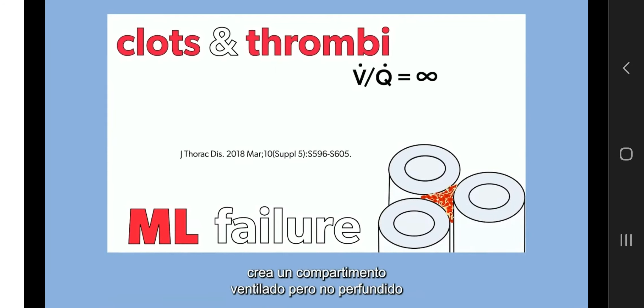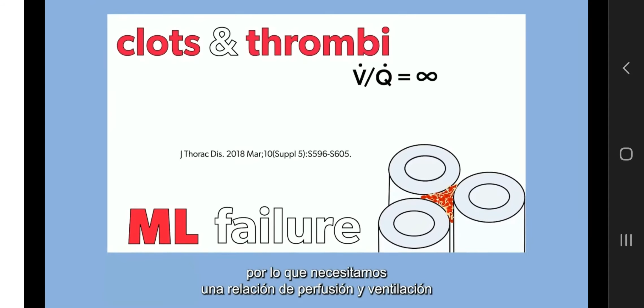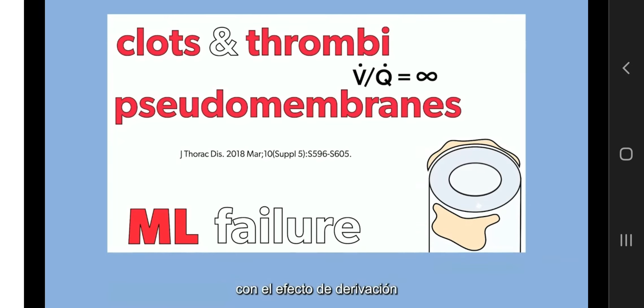Extensive clots and thrombi formation around fibers creates a ventilated but not perfused compartment inside the membrane lung with a dead space effect, so with a ventilation-perfusion ratio approaching infinity. Pseudomembranous deposits on the wall of hollow fibers may completely prevent gas exchange with a shunt effect and ventilation-perfusion approaching zero. These conditions are characterized by worsening of membrane lung efficiency, impairing both oxygen transfer and carbon dioxide removal.